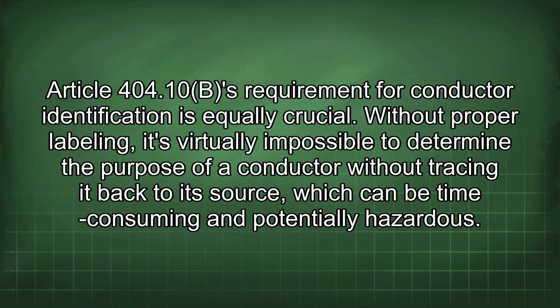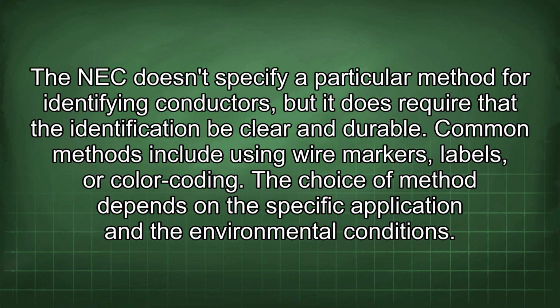Article 404.10b's requirement for conductor identification is equally crucial. Without proper labeling, it's virtually impossible to determine the purpose of a conductor without tracing it back to its source, which can be time-consuming and potentially hazardous. The NEC doesn't specify a particular method for identifying conductors, but it does require that the identification be clear and durable. Common methods include using wire markers, labels, or color coding. The choice of method depends on the specific application and the environmental conditions.